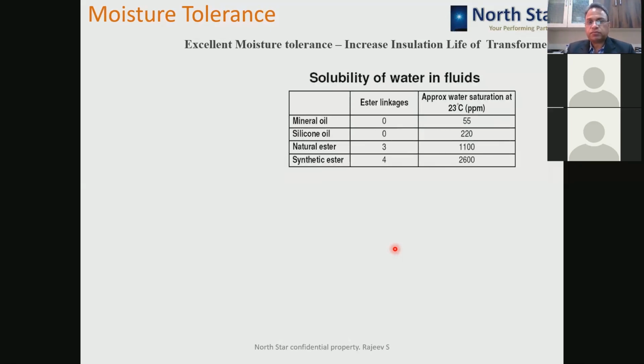So if we look at the solubility of water in fluids, in mineral oil, you can see here, this is ester linkages and approximate water saturation at 23 degrees centigrade in ppm. Okay, in mineral oil there are no ester linkages, so only 55 ppm water can get dissolved at 23 degrees centigrade. So what we mean to say is that because of ester linkages, the moisture absorption capacity is improved. In silicone oil there are no ester links, so still you can have 220 ppm moisture at 23 degrees centigrade without affecting the electrical properties of that liquid.